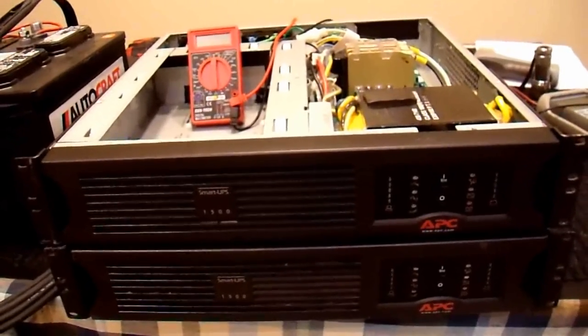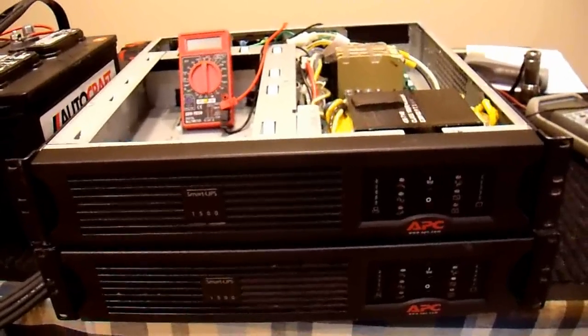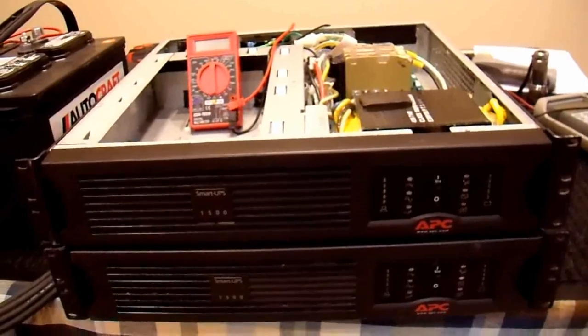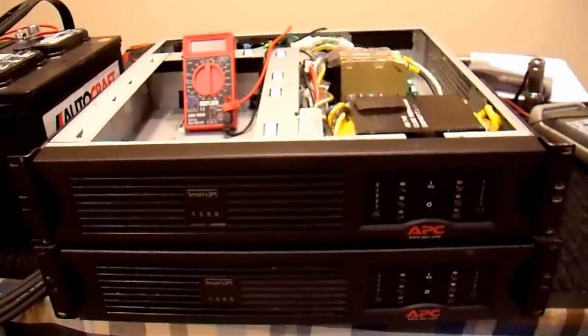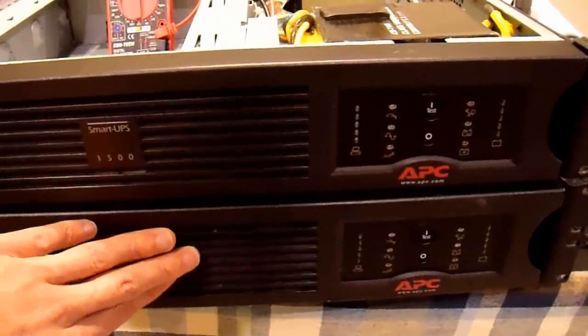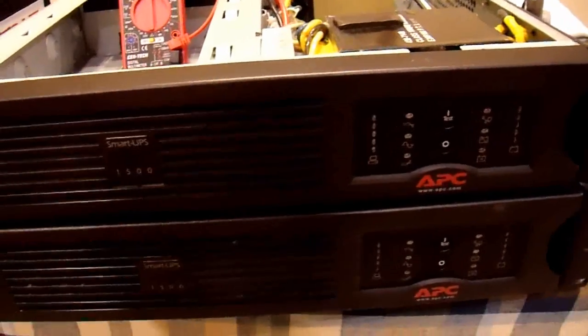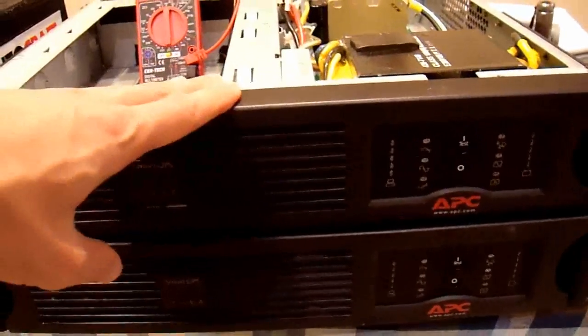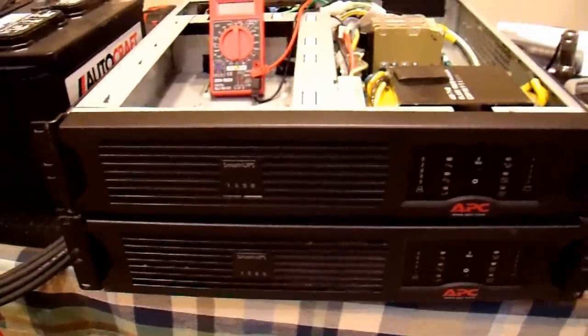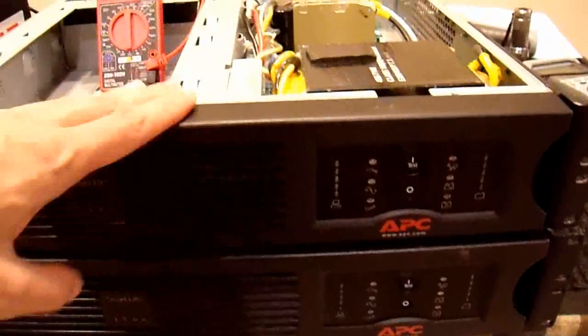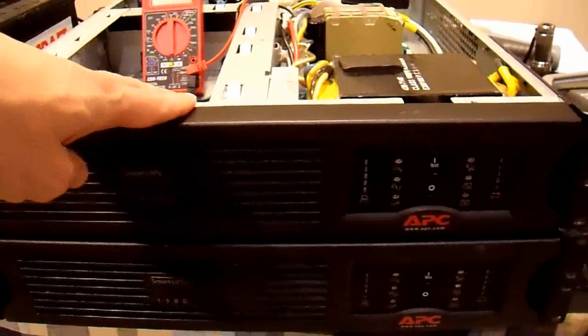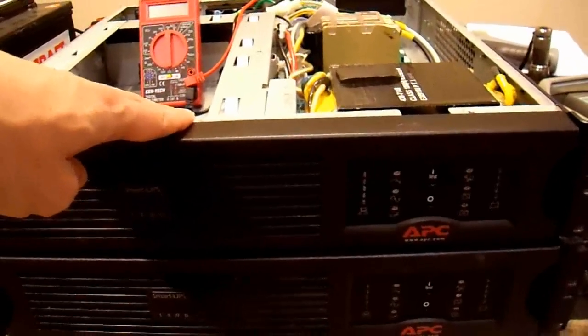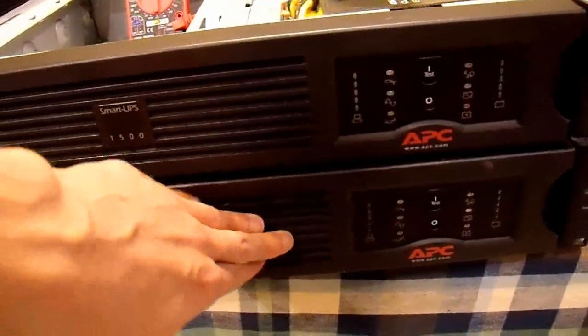So I need a way to synchronize these units together so that they both oscillate at exactly the same frequency and at exactly the same phase. Otherwise this strategy will not work. So how do I do that? Well, APC already has some of that built into them. They have a synchronized to mains feature. In this case, I don't want to have the UPSs synchronized to a wall outlet frequency. I want them to synchronize to each other. So I'm going to do that by saying that this one on the bottom is my master and this one on the top is the slave. Now I'm going to let the master oscillate at whatever frequency it wants to oscillate at, and this one is going to follow the master.